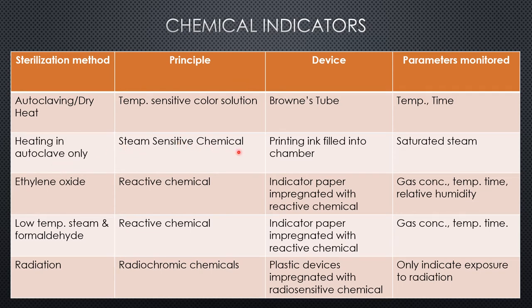For autoclave sterilization, an organic chemical in a printing ink is filled into a chamber or a carrier material. A combination of moisture and heat causes darkening of the ink, which serves as the indicator for sterilization. The parameter monitored here is saturated steam.